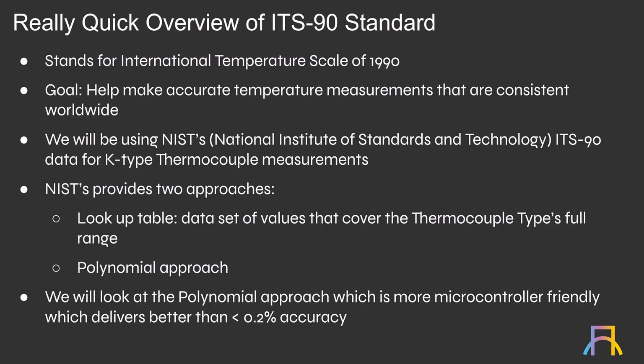Now, they provide 2 different approaches, whether we're talking about the standard or NIST data. The first one is the lookup table, which literally has a voltage-to-temperature value for every degree within the K-type thermocouple's range. If you make a measurement of a voltage, you can look it up in the table and get the temperature—very easy. The problem, though, is the table can be very bulky, so you have to store it in memory, hard-coded. Also, the table only covers integer values of temperature.